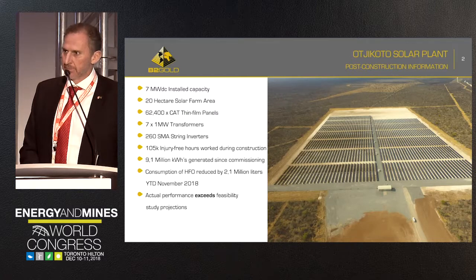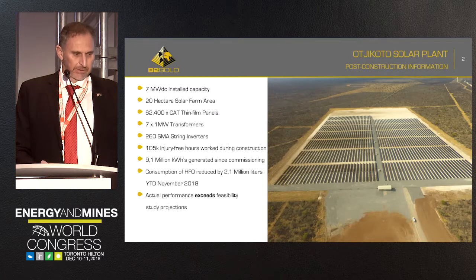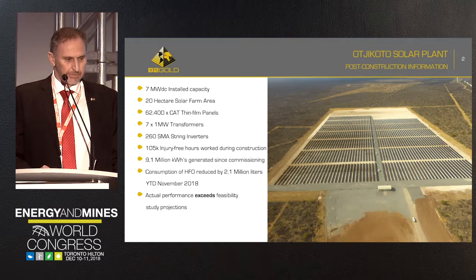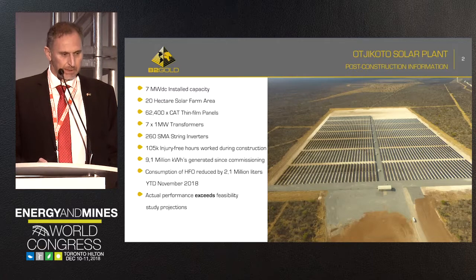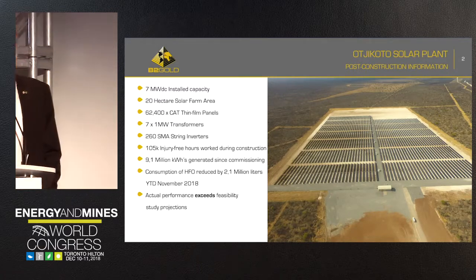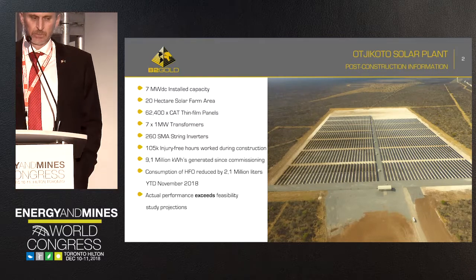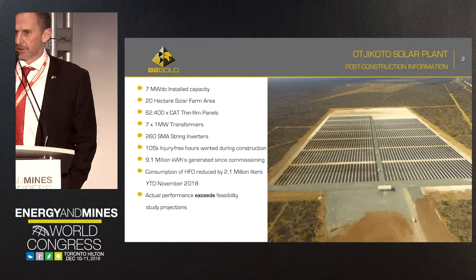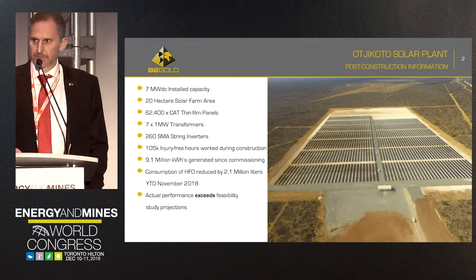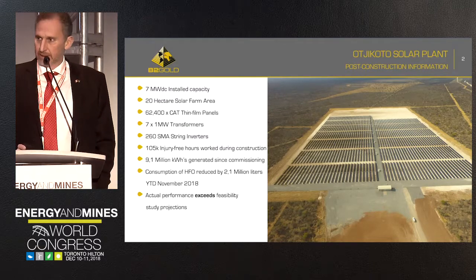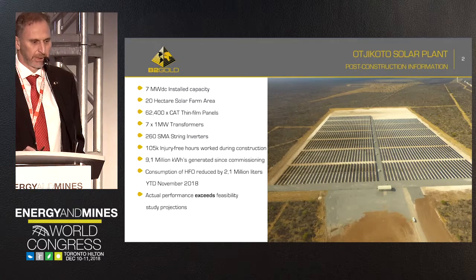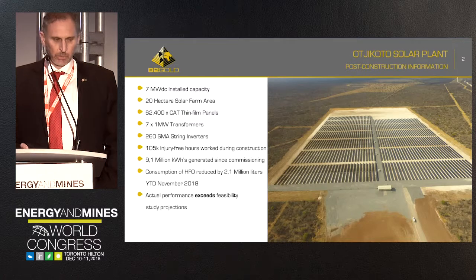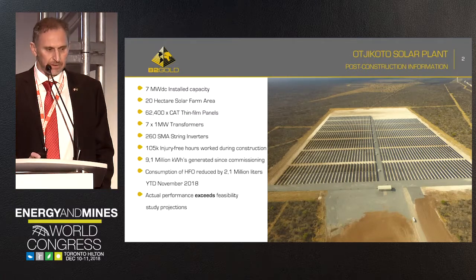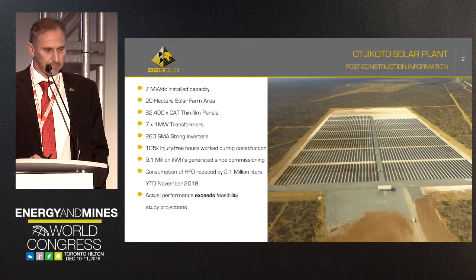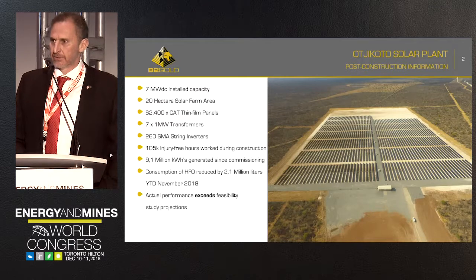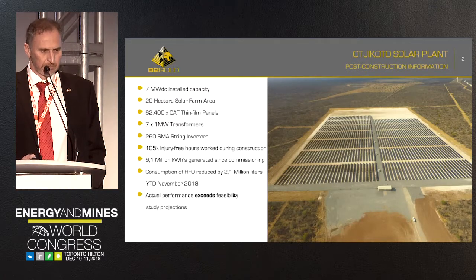So far we generated, since May, we commissioned in May this year, and it wasn't fully operational in May, so basically since June, the end of June actually, 9.1 million kilowatt hours has been generated since we started the plant. And the idea of the talk, as I spoke about last year, was to reduce the fuel consumption. We're an island producer, meaning we have our own power production generators, HFO, 24 megawatts installed. The idea was that we reduce our fuel consumption, which is obviously a huge cost on the mine. So we've saved so far since June 2.1 million litres of fuel. You can imagine the carbon savings as a result of that. That's up until the end of November. And the actual production results exceed the feasibility, which means I still have a job.